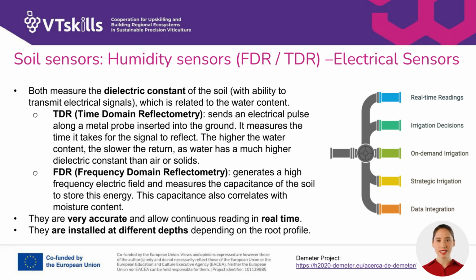How do they work technically? TDR, time domain reflectometry, sends an electrical pulse along a metal probe inserted into the ground and measures the time it takes for the signal to reflect. The higher the water content, the slower the return, as water has a much higher dielectric constant than air or solids.